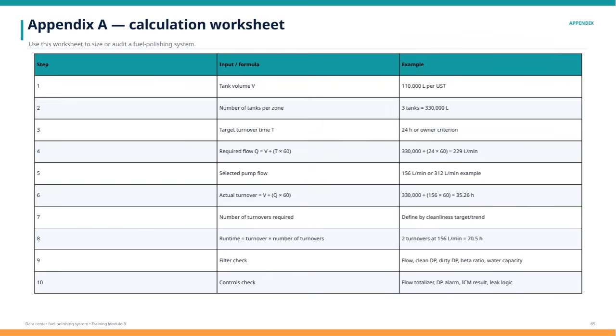Finally, it's important to check the filters for flow, clean and dirty differential pressure, beta ratio, and water capacity to ensure proper operation. Controls also need to be reviewed, including the flow totalizer, differential pressure alarms, ICM results, and leak detection logic.